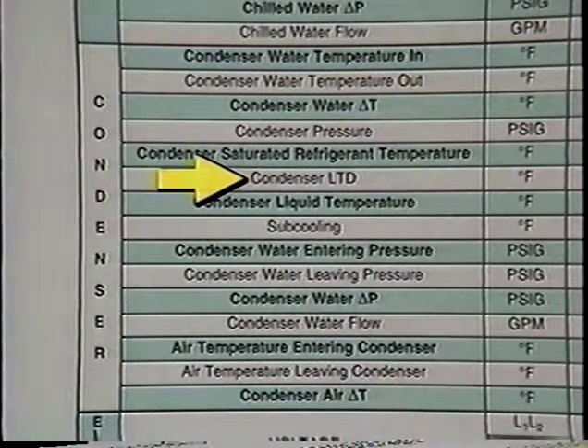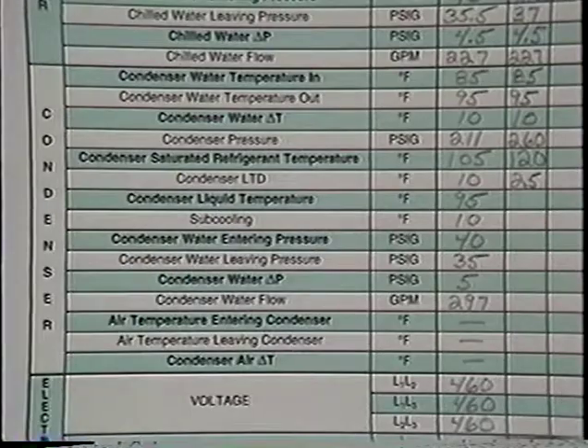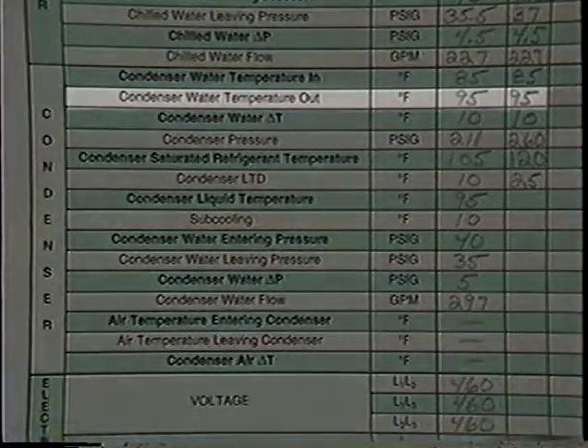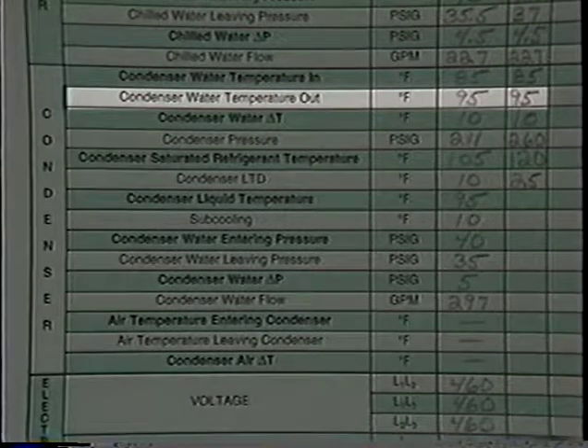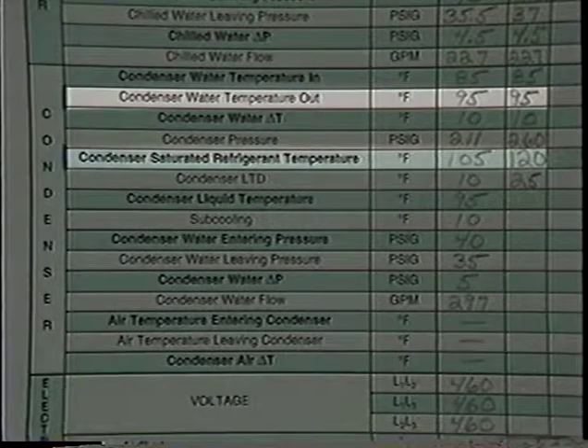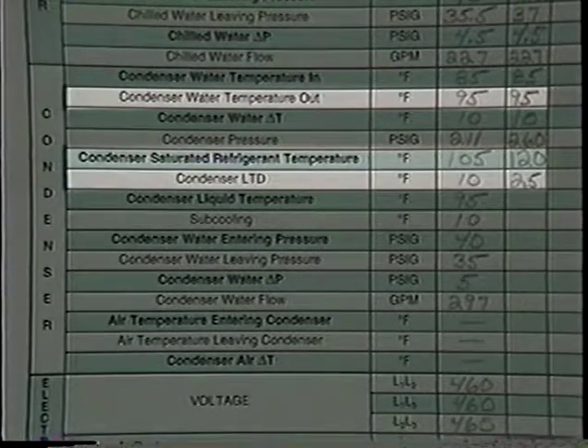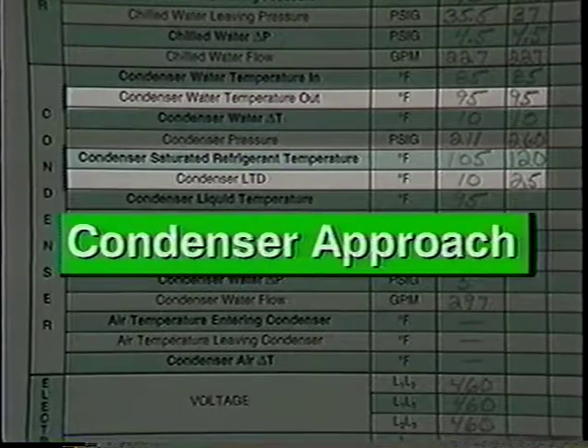Condenser leaving temperature difference, LTD. The condenser leaving temperature difference, or LTD, is found by subtracting the leaving condenser water temperature from the saturated condenser temperature. This also may be referred to as condenser approach.